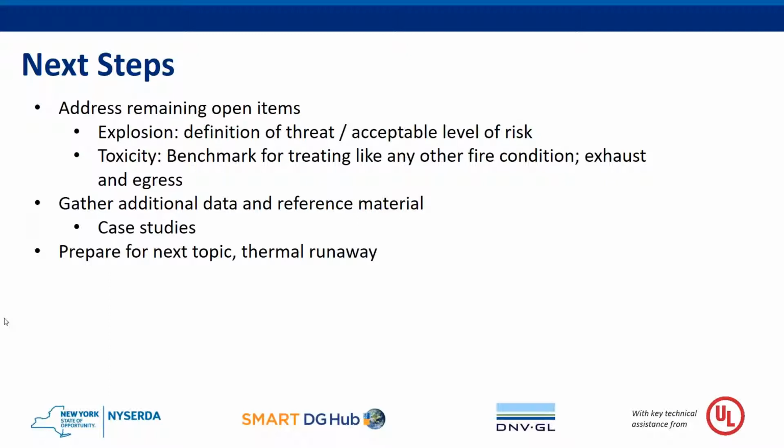Victoria, this is Jim again. I'm going to say this, and correct me if I'm wrong. If you're a manufacturer and you've got models A, B, C, and D of a particular design, and Model D, just being a little mythical here, has 4 modules in it, Model C has 3 modules, etc. At UL, while we would love to take all your money to test all your designs, clearly, if we test the unit that has the 4 modules in it, we're going to grandfather the ones that have 1, 2, and 3 because you've done a worst case scenario. The goal here is not to be a burden to people, but let's just make sure we've got the worst case data. Is that accurate, Victoria? Yep, that is exactly correct. Yep. Thank you, Jim.